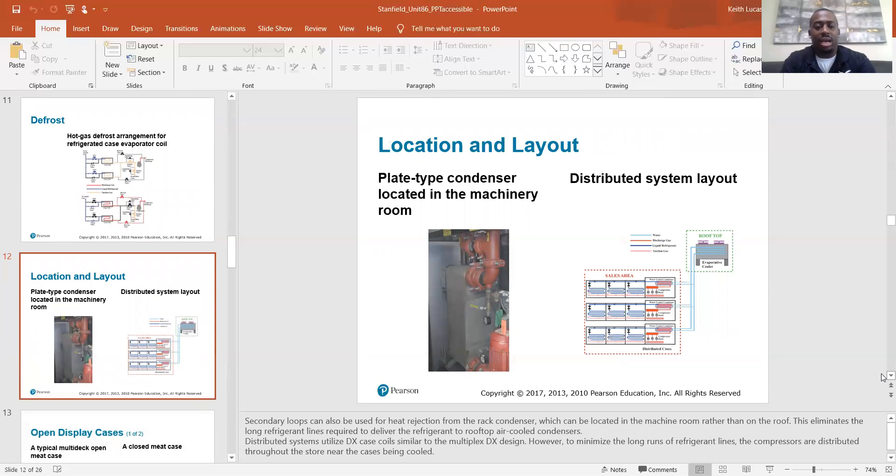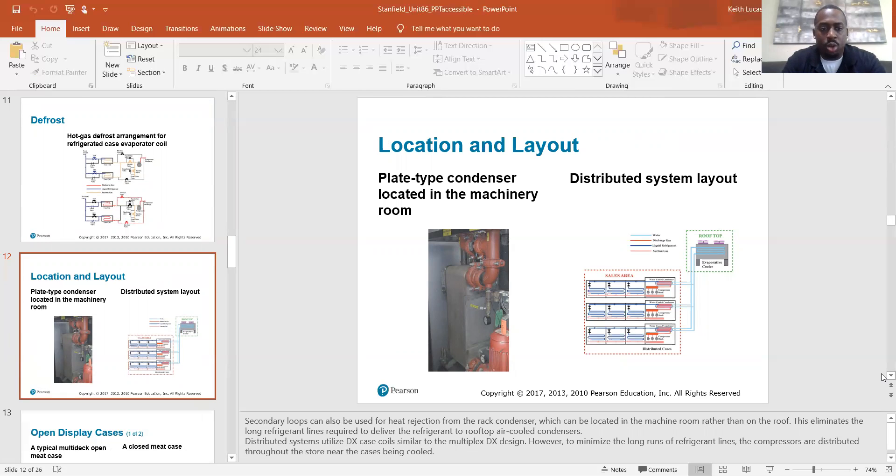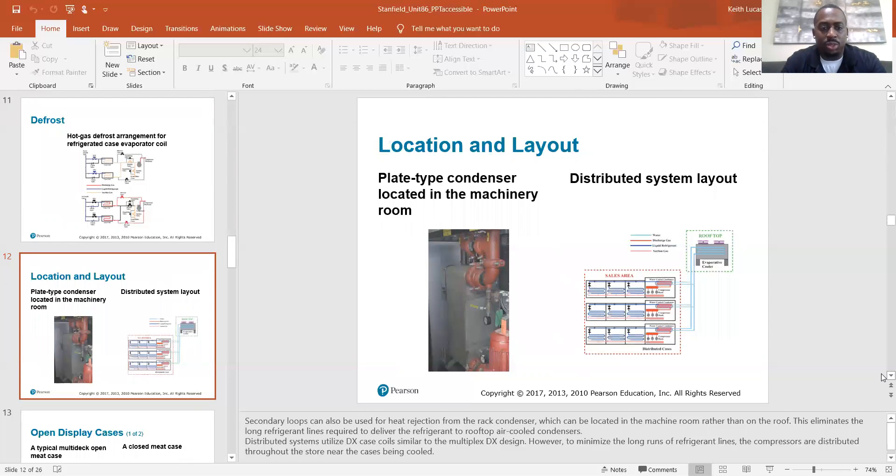Location and layout. Secondary loops can also be used for heat rejection from the rack condenser, which can be located in the machine room rather than on the roof. This eliminates the long refrigerant lines required to deliver the refrigerant to rooftop air-cooled condensers. Distributed systems utilize DX case coils similar to the multiplex DX design. However, to minimize the long runs of refrigerant lines, the compressors are distributed throughout the store near the cases being cooled.